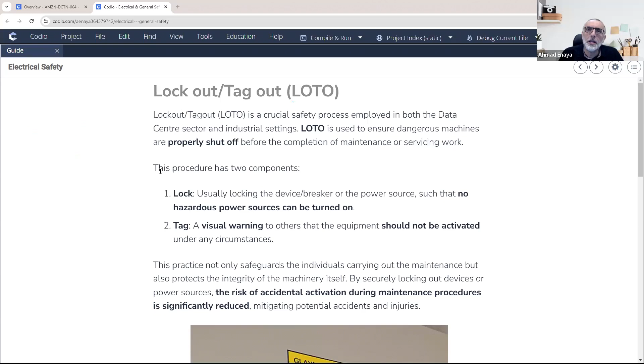There's an easy concept called LOTO, which means before you do any maintenance on electrical devices, you disconnect the power, you lock it out, and you tag it. So others know for sure that you are working on this device right now. When you tag it, you add information: your name, what time you started, what you are doing, how long this will take. So anyone who sees the equipment disconnected knows for sure that someone is working right now on this equipment. This is the name and contact number for that person, and these are the details of the work they are doing right now.